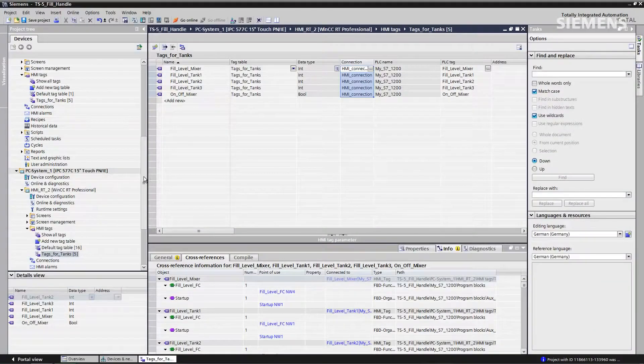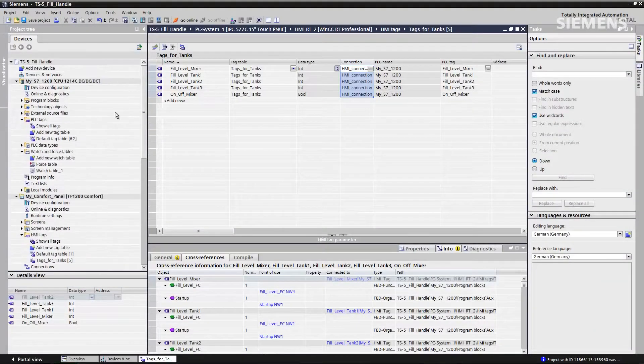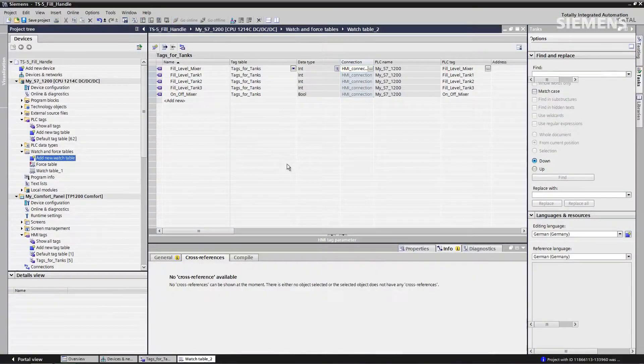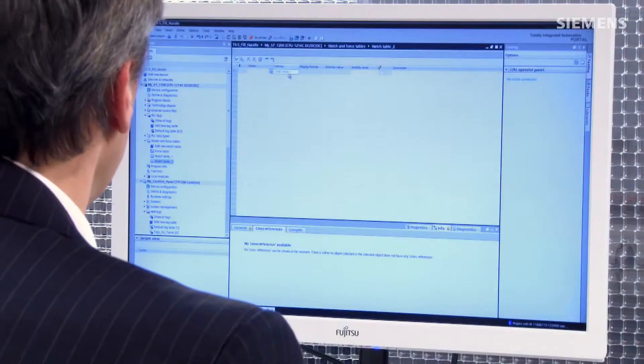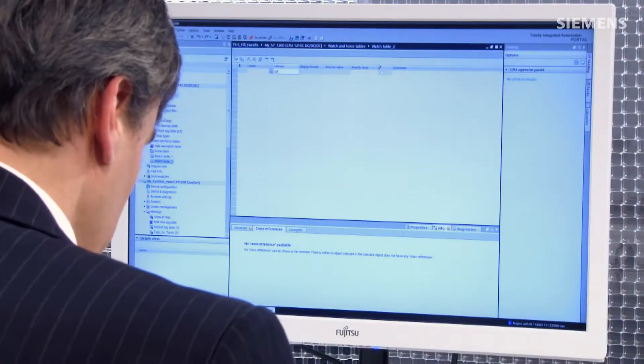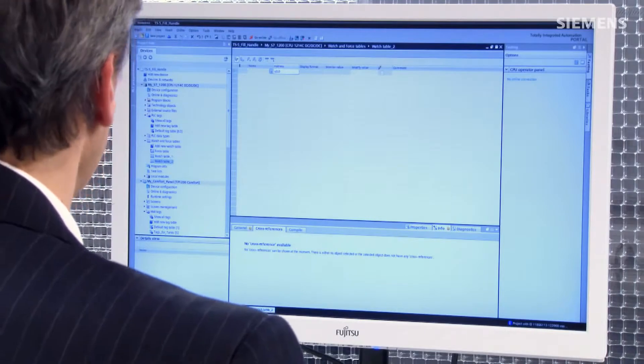So how does this function help us build watch tables? If I go up to the controller, double click on the add new watch table, go to the address field, and choose the actual output bit I want to use, Q0.0, click enter. The associated tag with that bit is automatically pulled into place.